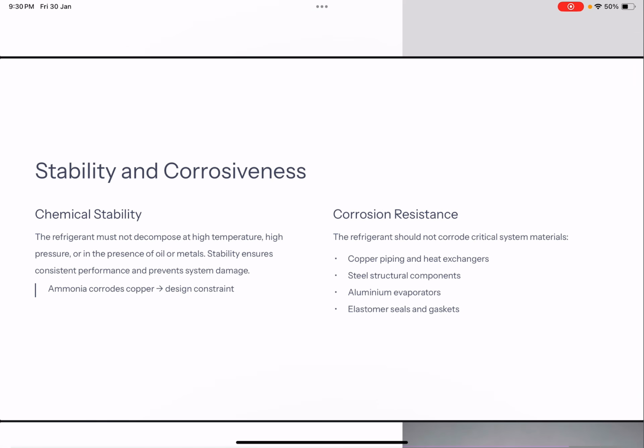One important thing is that the refrigerant, whichever we use, has to be chemically stable. By chemical stability, what we mean is that the refrigerant should not decompose at a higher temperature, because if it decomposes, then it would have an adverse impact on the system. It would corrode the materials which are used. For example, ammonia corrodes copper, which is a design constraint, and we cannot use copper wherever ammonia is used as a refrigerant.